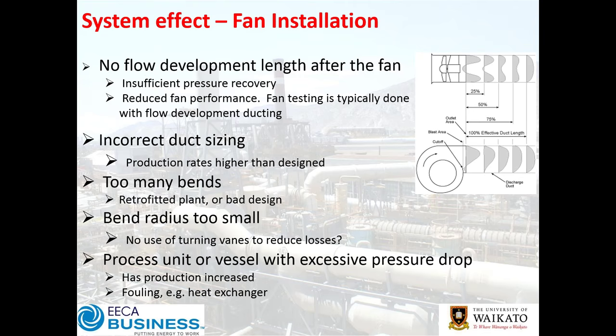Fan performance or fan curve is based on a specific gas — typically air — at standard conditions, perhaps 20°C, one atmosphere. If it's a hot exhaust gas fan running at 100–200°C, that's quite significantly different. Hopefully your supplier is providing a fan curve for the expected operating conditions, not standard air. These things are all based on full pressure recovery.